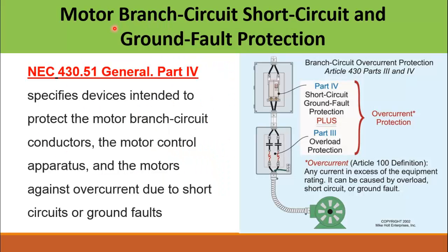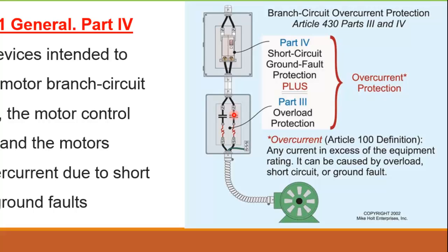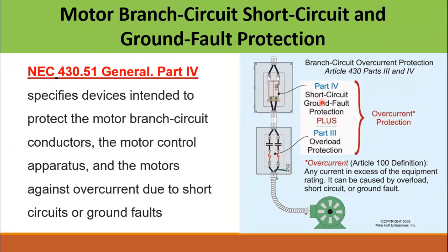For the motor branch circuit short circuit and ground fault protection, here you can see the branch circuit for the motor load. This is the circuit breaker — or it can be a fuse — that will provide the short circuit or ground fault protection. After the contactor there is an overload device which provides overload protection for the motor. So there are two types of protection: first is overload protection, and the other is short circuit and ground fault protection.